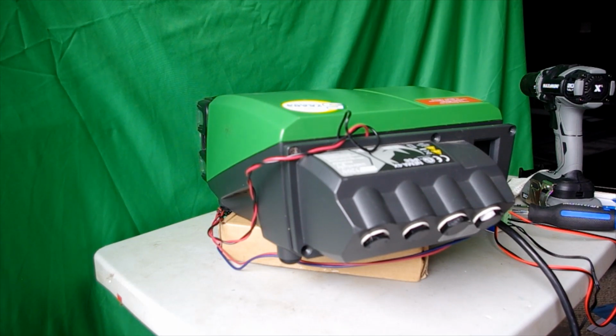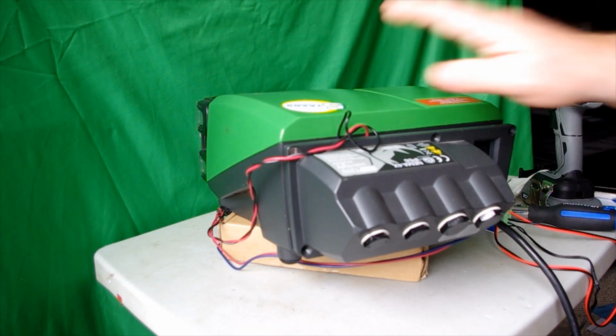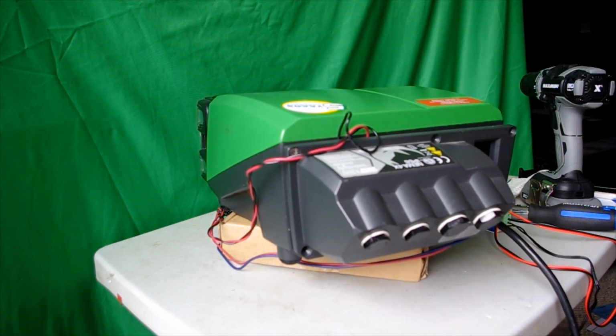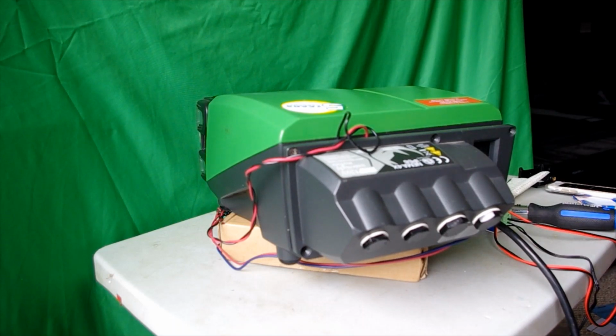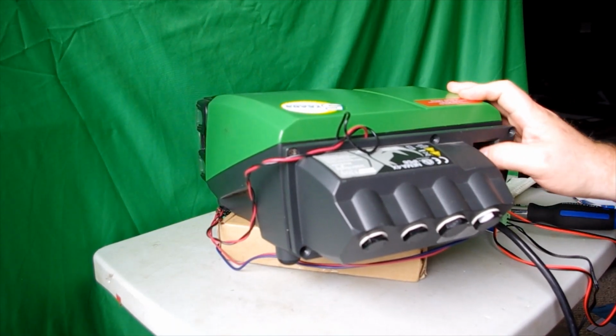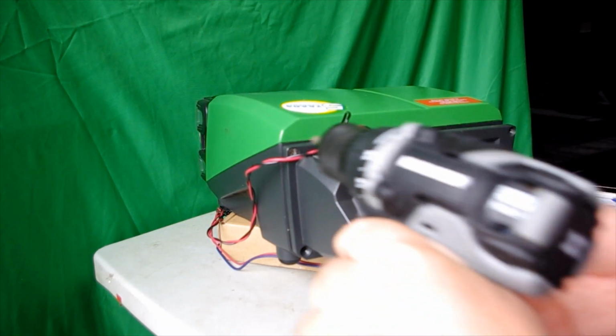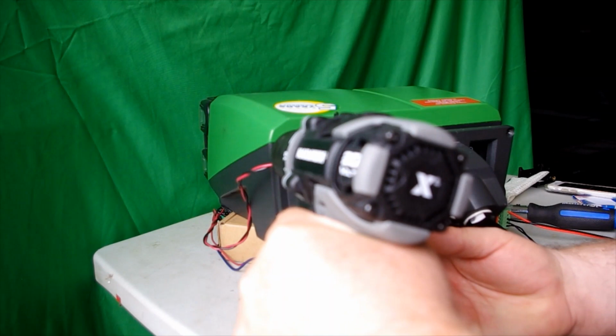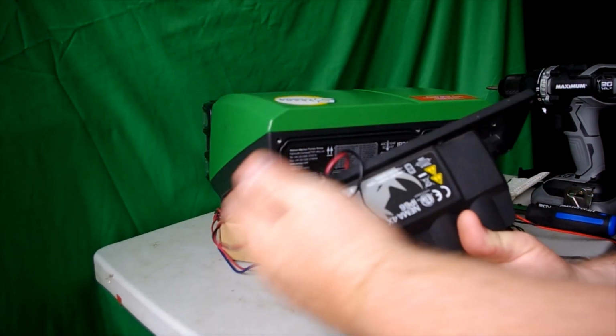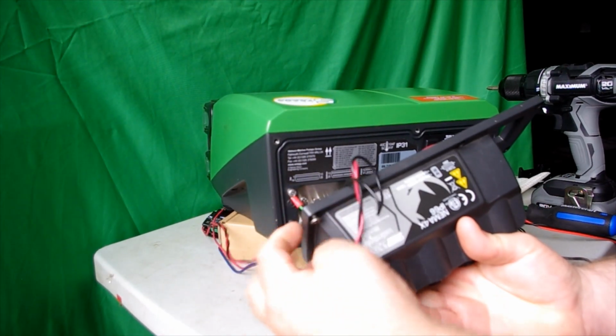the pump. So in this situation here, let's say we're dealing with a Watson-Marlow Qdos pump. We would first want to take out the NEMA module, so you would stop the pump. Then you would take off your NEMA module. For video purposes, I've already taken this off. I just have one screw left. Note that the screws are captive, or not captive, so they will fall out. So you might want to just manually go and grab the screw or tip it out so that it's not going to fall on the floor.